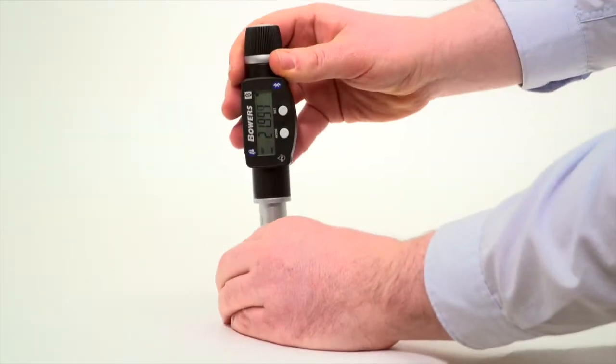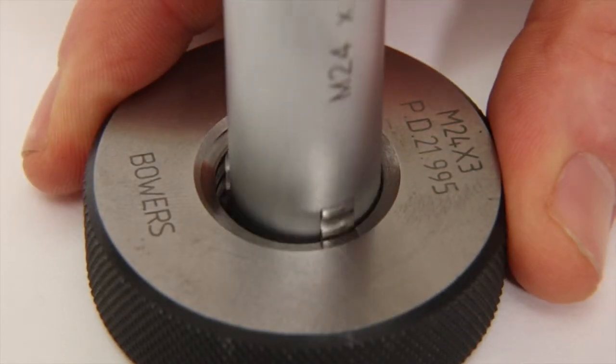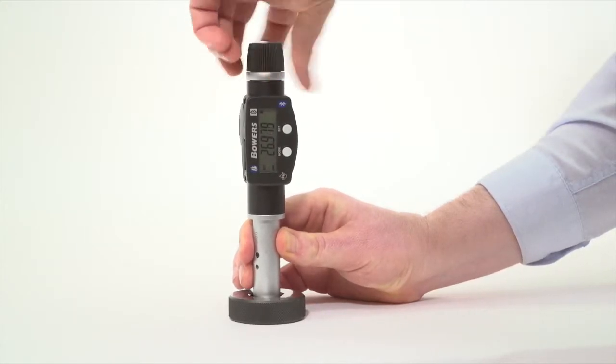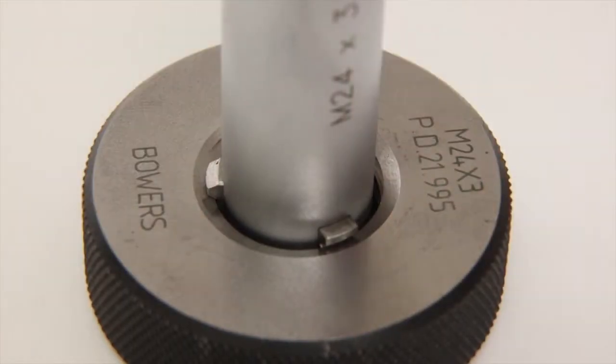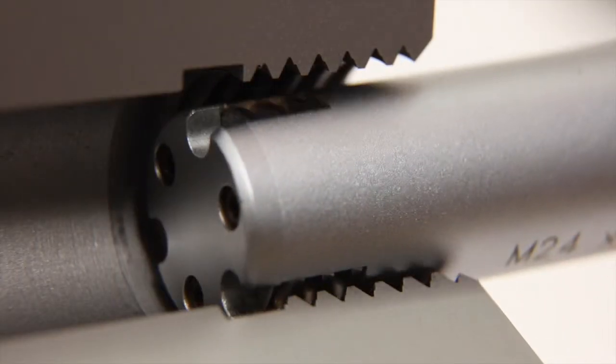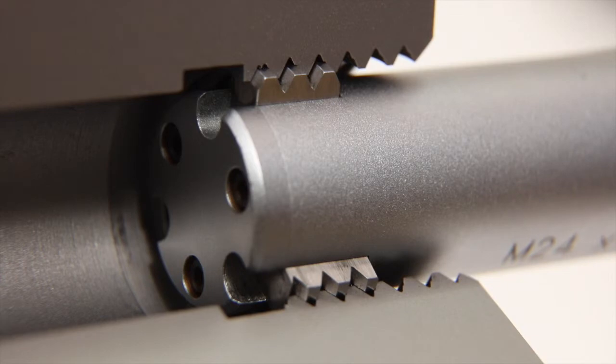Gauges are calibrated in the supplied setting ring, referencing the display to the actual pitch diameter as marked on the ring. The part can then be measured. The head enters the bore and then takes an actual reading of the effective pitch diameter, contacting on the flank area of the threads.